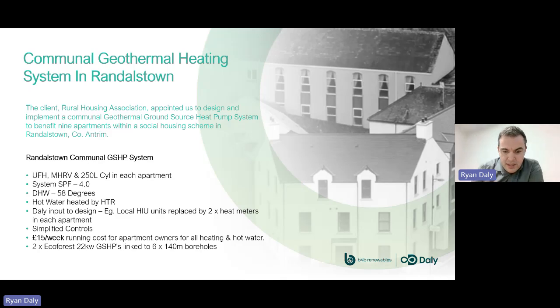So you're actually one of the first trades in on that project to do the boreholes before any of the civil works was done in the building. Each apartment then has underfloor heating. They have a mechanical heat recovery ventilation system and a 250-litre hot water tank. The system SPF is averaging around 4, with domestic hot water heating it up to 58 degrees, probably a wee bit higher, but then we have to allow for that slight drop off in terms of circulation of that heated water up through the building. There would be a 3 to 4 degree loss in that.